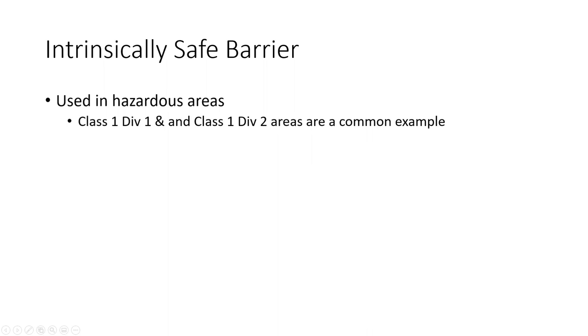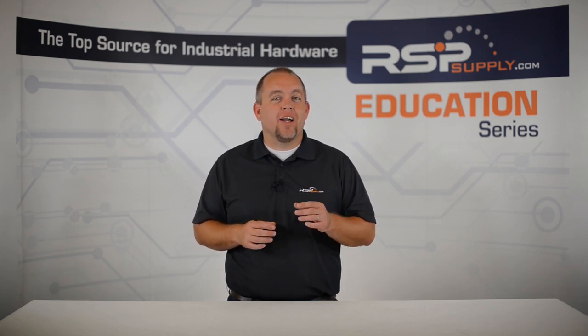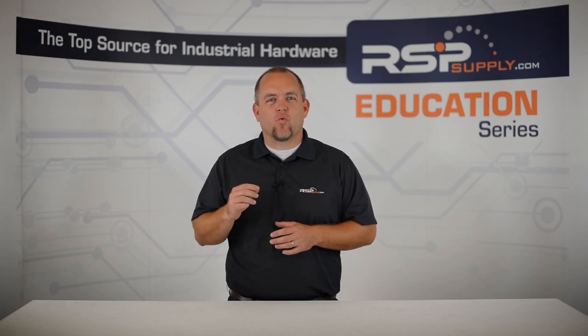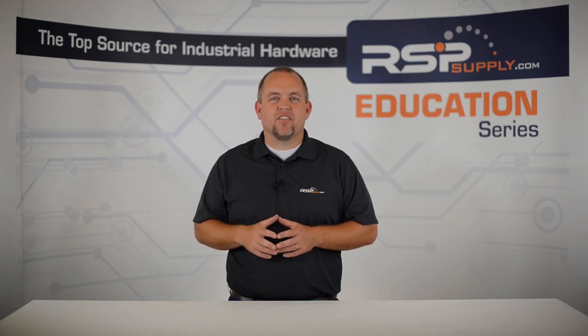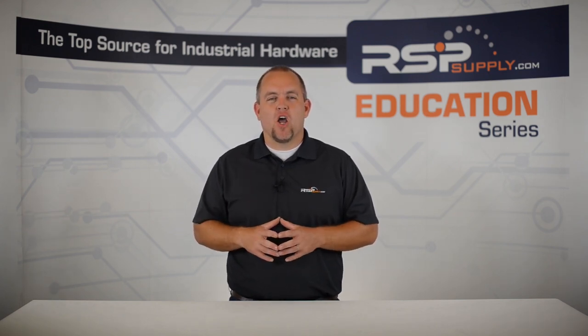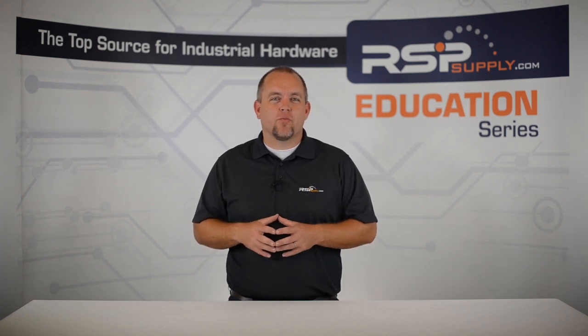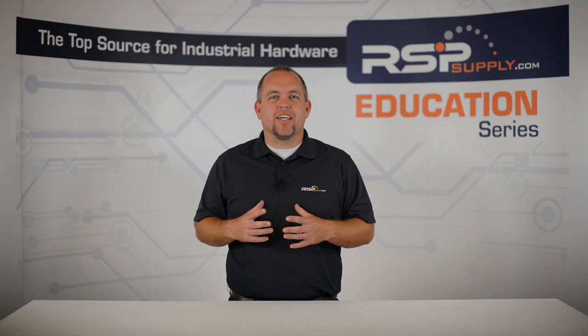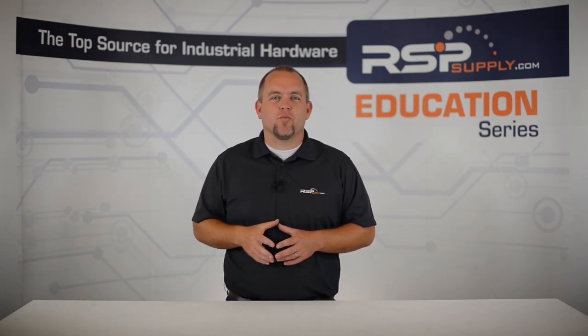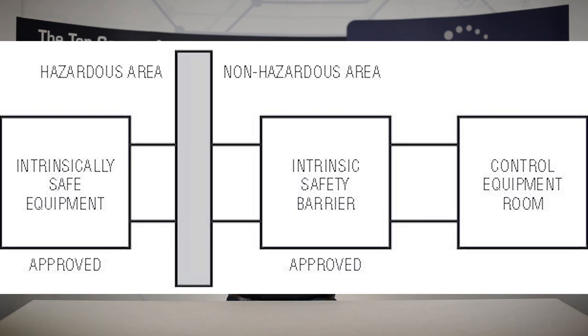As mentioned before, when dealing with control circuitry in hazardous areas such as Class 1 Div 1 and Class 1 Div 2 environments, any instrumentation that is being used has the potential to short circuit, which can lead to deadly explosions. In order to reduce this risk, many safety standards have been put in place that limit the chances of a short circuit, or at the very least can contain the explosive effects into a small area. Typically in these types of scenarios, the power that is being fed to the instruments in question is being supplied from a different location — a location that is not at risk of explosion if a short circuit occurs.